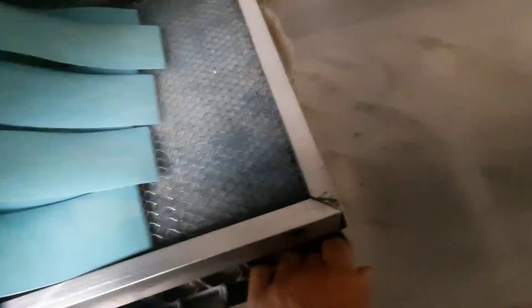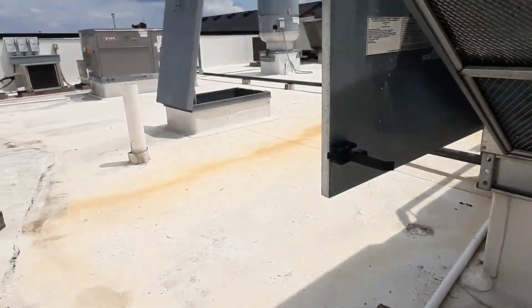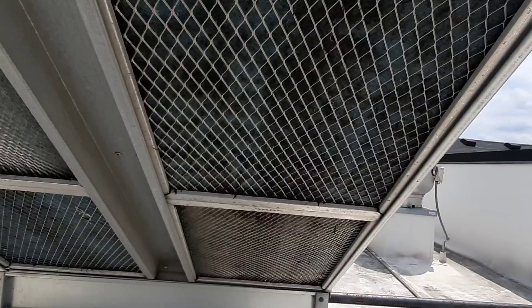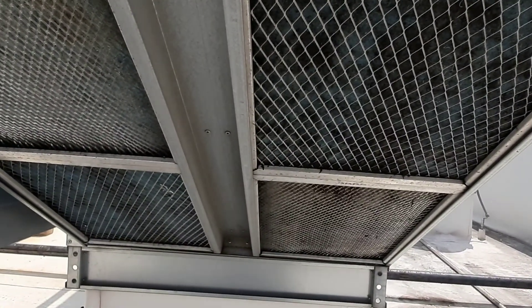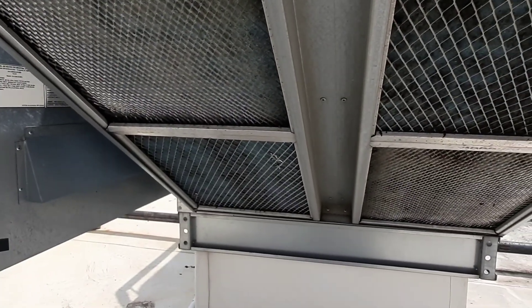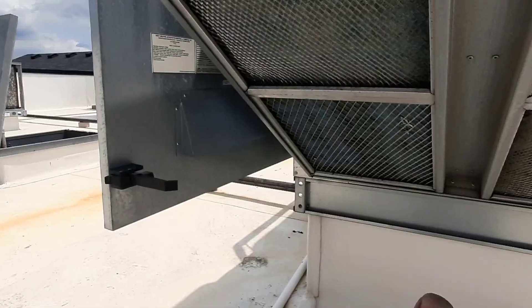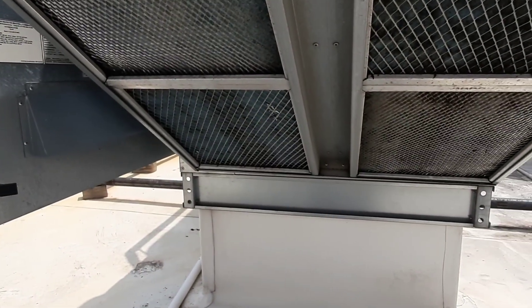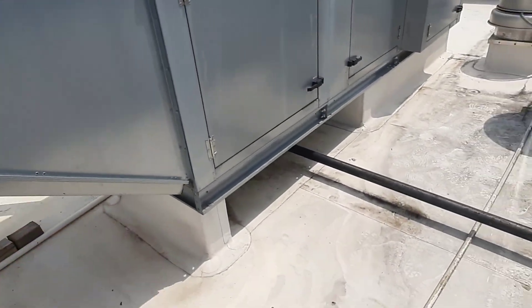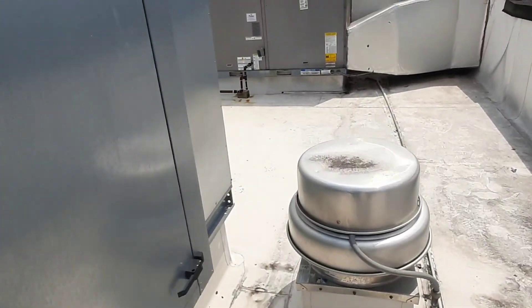So much easier than a water hose. We've got a little airflow. The VFD's right on the cook line - it's running at about 50 hertz. This is a CaptiveAire system, set up and supposed to be correct from CaptiveAire. I don't want to go adjusting too much and throw things off, but I've got humidity issues. I went to look at the thermostats - all the thermostats are satisfied except for the kitchen. Obviously the kitchen's always going to be a little warm.